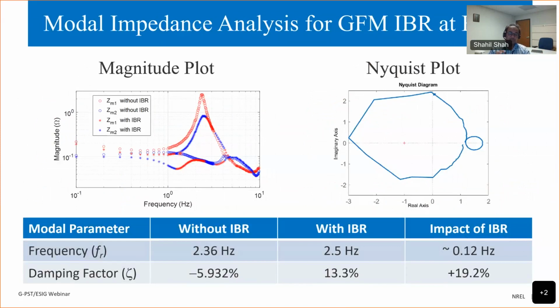As I said before, by measuring the impedance of the rest of the network and the IBR plant separately, you can really isolate the dynamics of the IBR. Here we are showing the modal impedances with IBR and without IBR. The circles represent without the IBR plant, or basically without this grid forming inverter at bus 6, and the stars show the modal impedance with IBR.